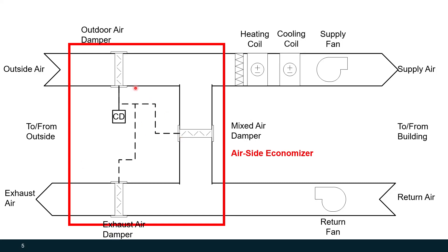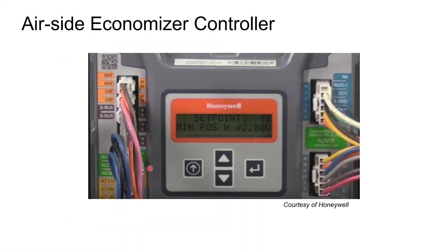These dampers can work in tandem to provide outside air for free cooling when we need it. They are wired together, as shown by these dashed lines, to work together to provide that free cooling. This is an air side economizer controller. All the dampers would be wired in here along with temperature sensors for the outside air temperature (OAT) and mixed air temperature. Sometimes we'll also use humidity sensors, and we'll get more into that in a few minutes.